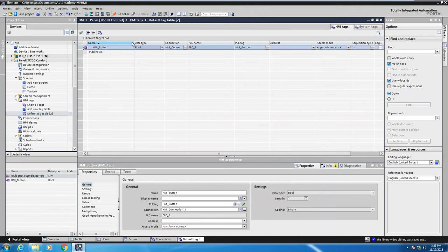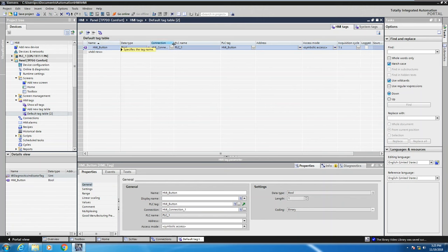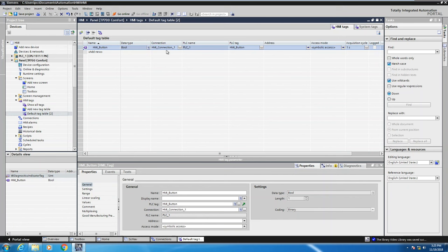So in this particular case, you can see here's the connection, here's my PLC tag, so it's using symbolic address. It's all name based at this point to be able to access the tag information. So the connection between the comfort panel and the S7-1500 has been established.